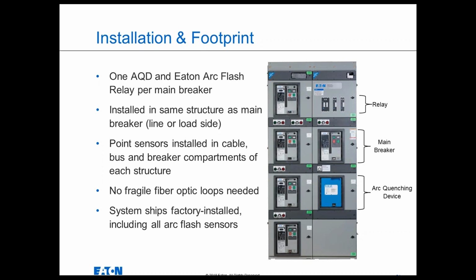And again, we use wired point sensors, not fragile fiber optic loops. There are a couple benefits to that. First, the wired point sensors can be installed in the factory, and so the system can be fully tested before the switchgear ships. Whereas typically, if fiber optic is being used as a light detection sensor, it needs to be installed in the field because it doesn't span shipping splits very well. So essentially, all the shipping splits of the switchgear need to be set down in the field. Everything needs to be cabled up, and then the fibers run. And that prevents the system from being fully tested at the factory. So again, that's why Eaton has chosen to use wired point sensors. It just improves the reliability of the system and ensures that it'll work as designed when it reaches the field.